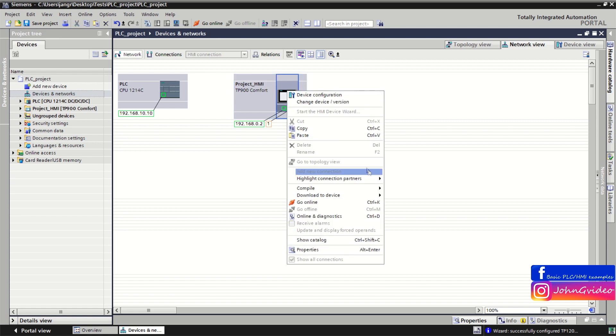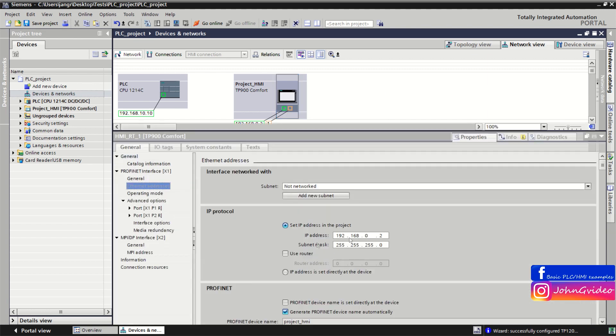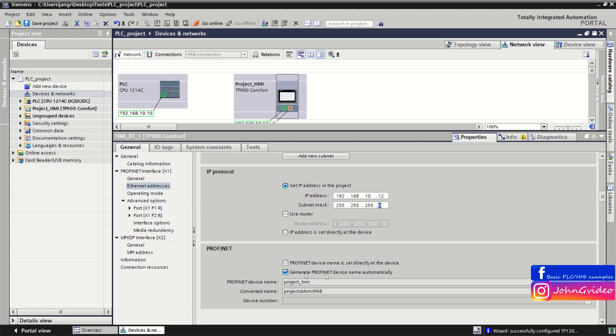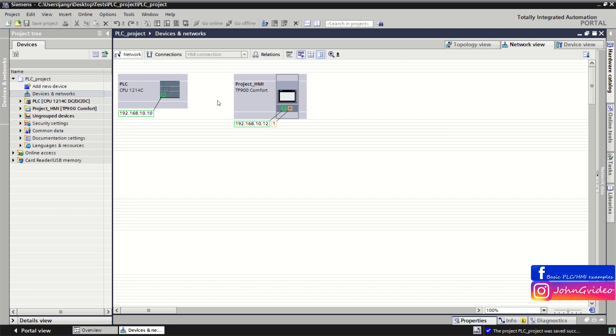First we check the IP address of the devices. Click on the HMI device in your hardware configuration, choose Properties, and change the IP address of the HMI to be on the same subnet as the PLC. For example we use this IP address and subnet mask. You can also change the Profinet device name — we generate it automatically, but you can also change it manually, for example to 'my-HMI'. Save it.